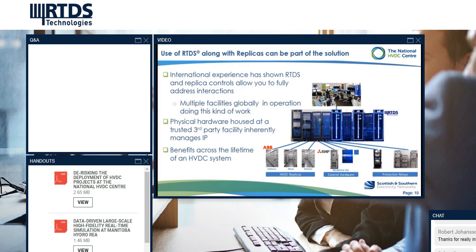And perhaps a little mention of AC protection relays, which would seem an unusual area to mention, but I will. AC protection relays each have their own algorithms to determine both noise and areas of potential maloperation to avoid, and equally determine, from polar impedance behavior and a range of other behaviors depending on the relay, how to trigger in response to a given fault condition. That's important both for the speed of the relay's operation in protecting the AC system, but also for discriminating between protected areas of the AC system.